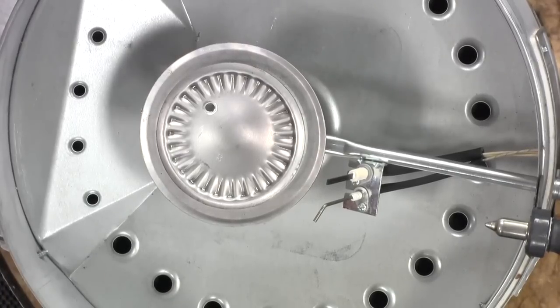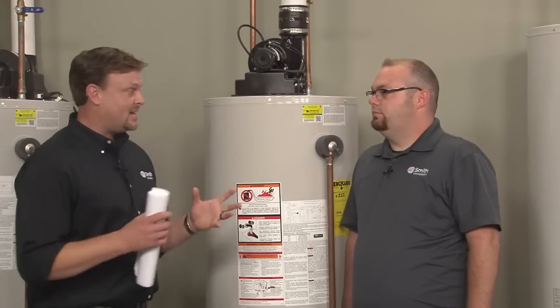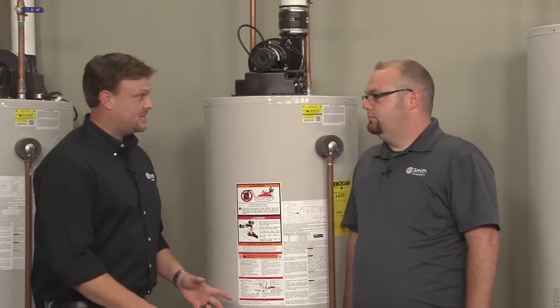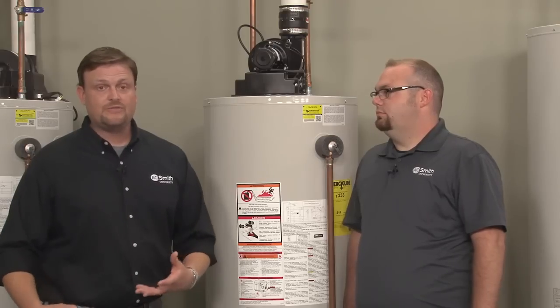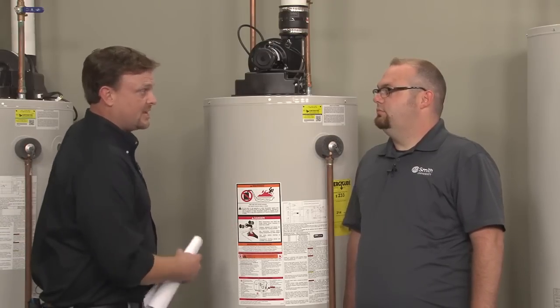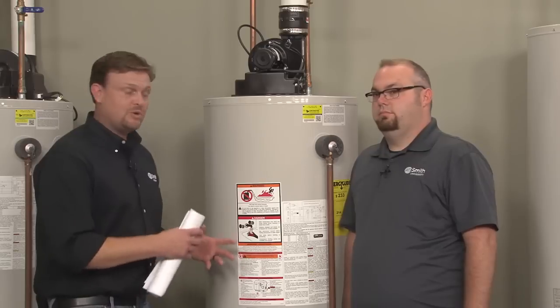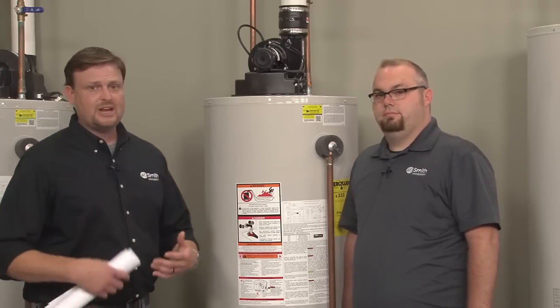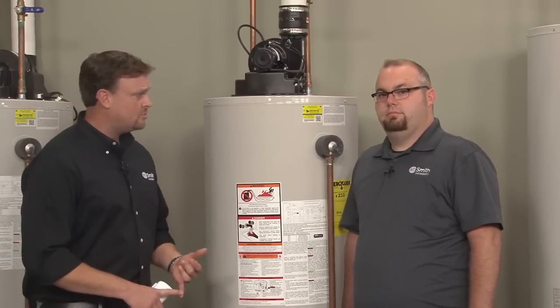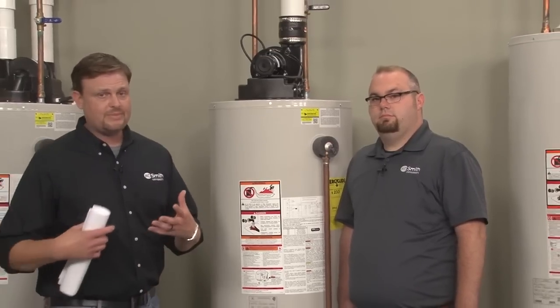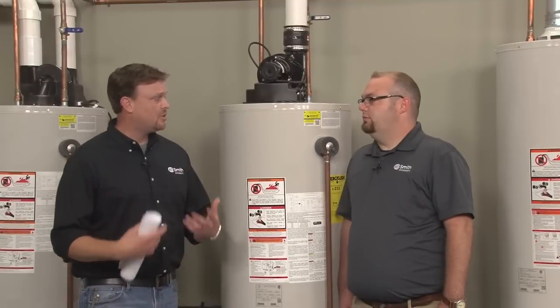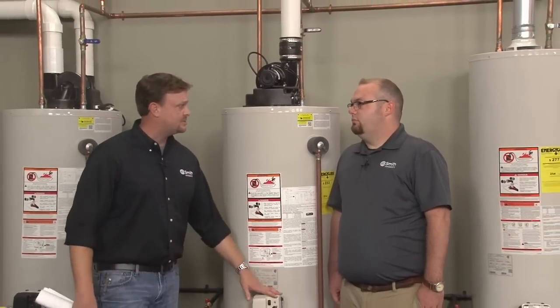Correct. That's great. Now, if I go up to the unit, I don't see a flame and it tries 3 times and then goes out. If I don't see a flame, then I know it's something to do usually with gas. So I'm going to go down the gas road. I'm going to make sure that nothing's closed off, my shutoff valve's not off, and I don't have air in the gas line. I'm going to do whatever I have to do to get that gas to the water heater to get it to work properly.